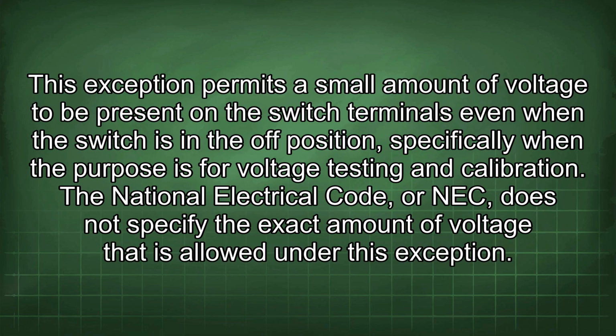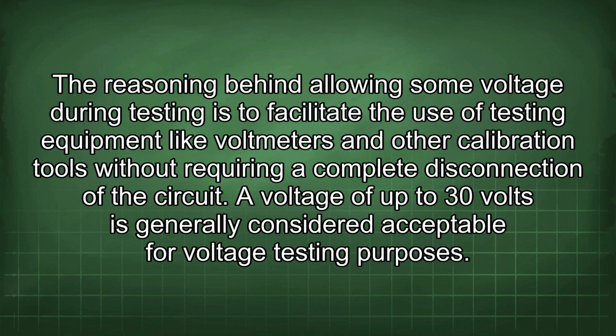This exception permits a small amount of voltage to be present on the switch terminals even when the switch is in the off position, specifically when the purpose is for voltage testing and calibration. The National Electrical Code, or NEC, does not specify the exact amount of voltage that is allowed under this exception. The reasoning behind allowing some voltage during testing is to facilitate the use of testing equipment like voltmeters and other calibration tools without requiring a complete disconnection of the circuit.